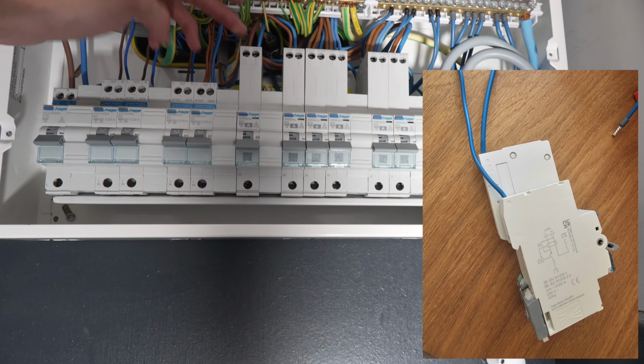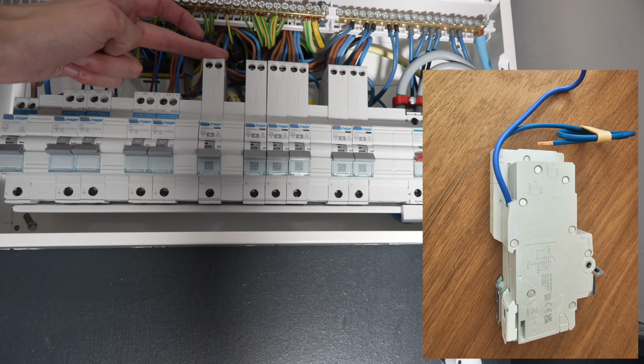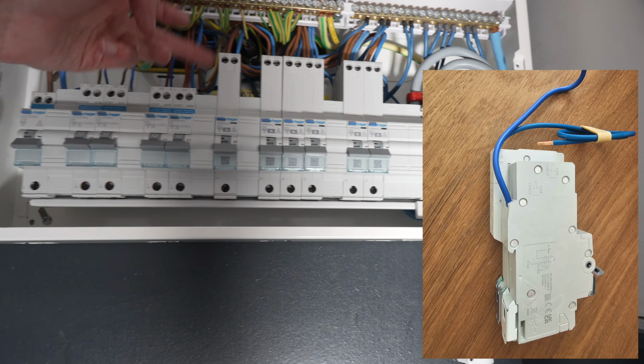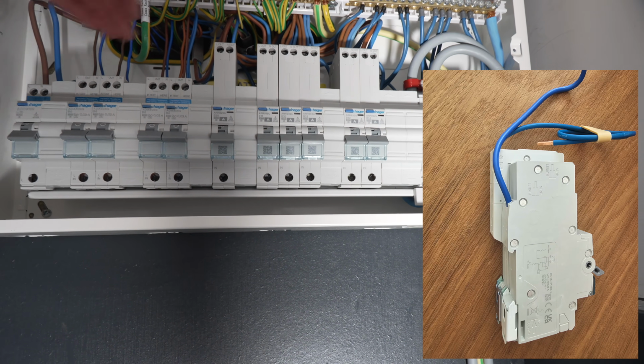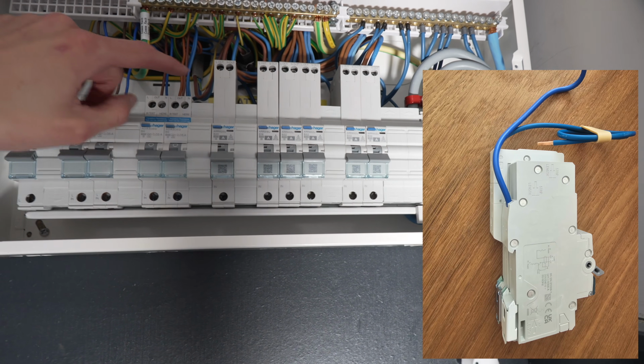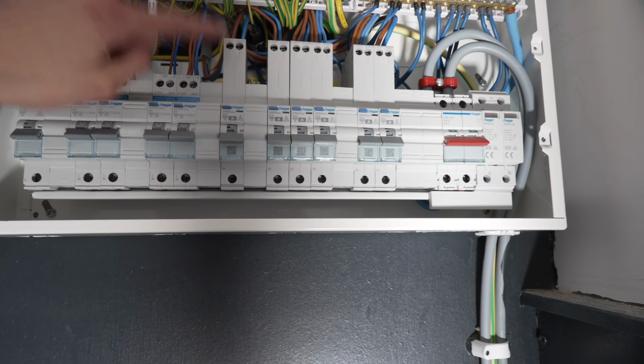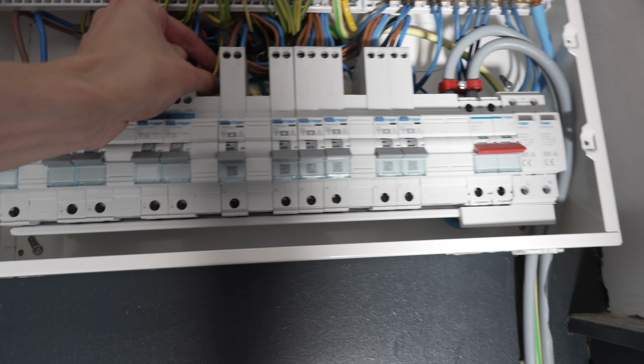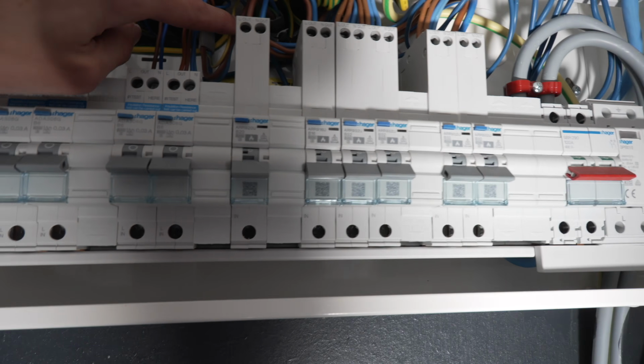You can see compared to a standard, a miniature RCBO, they're way taller, and compared to even a full-size Hager RCBO, they're still way taller, and they're way deeper as well, front to back, so there's no space behind them to stash cables, which makes it a little bit awkward and not very neat. So for this one here that feeds the comms rack, I should be able to get a CT on that just because the wire's in there, so I should be able to squeeze it in.